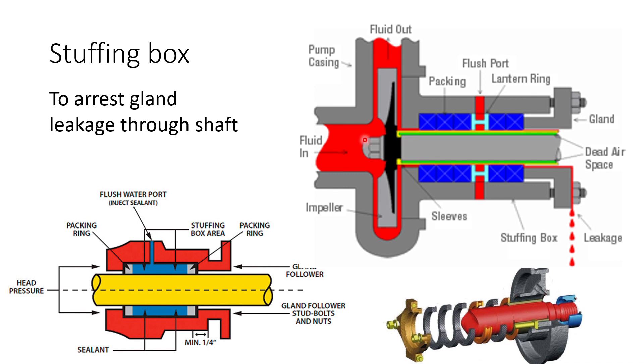Now let us talk about the stuffing box or the seal on the shaft. When the shaft is coming out, there will always be some clearance between the shaft and the body of the pump, and liquid will try to come through. For that reason, we put gland packings. We can also see a lantern ring here, from where the seal flushing fluid comes in and does the sealing of this ring so that it does not get overheated. Through these two nuts, we can adjust the compression of the seals so that leakage is avoided.